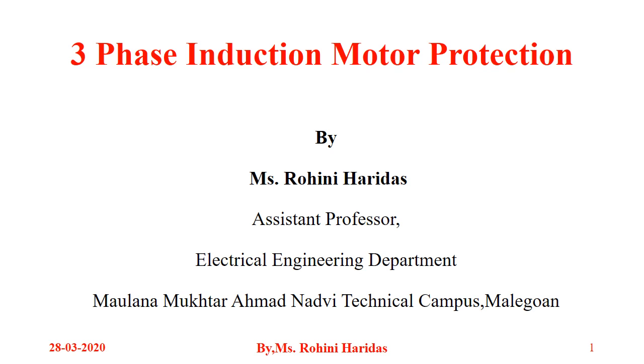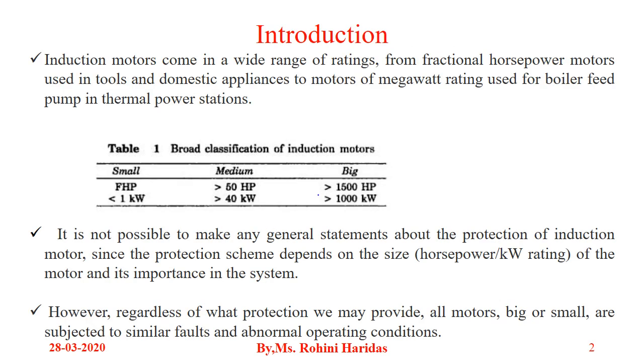Today we are going to discuss three-phase induction motor protection — Unit 4. Induction motors come in a wide range of ratings, from fractional horsepower motors used in tools and domestic appliances to motors of megawatt ratings used for boiler feed pumps in thermal power stations. The broad classification of induction motors: less than 1 kW is a small motor, greater than 40 kW is a medium size motor, and greater than 1000 kW is a large size motor.